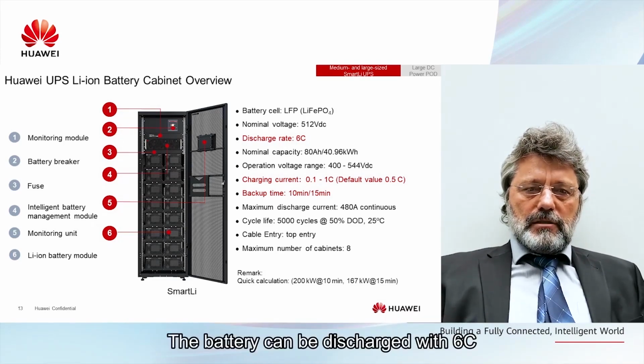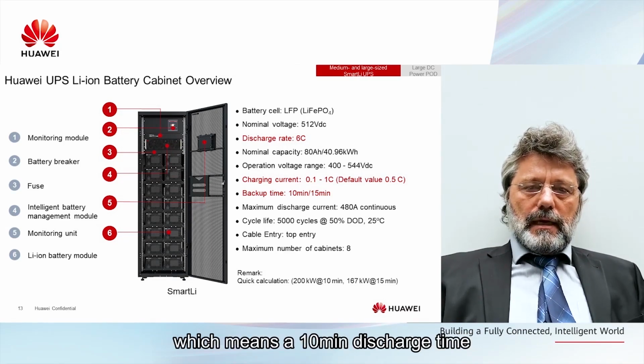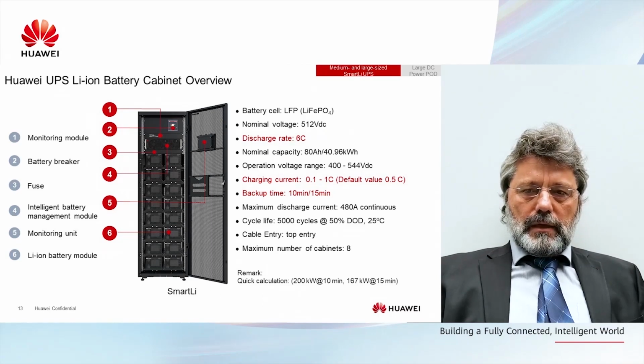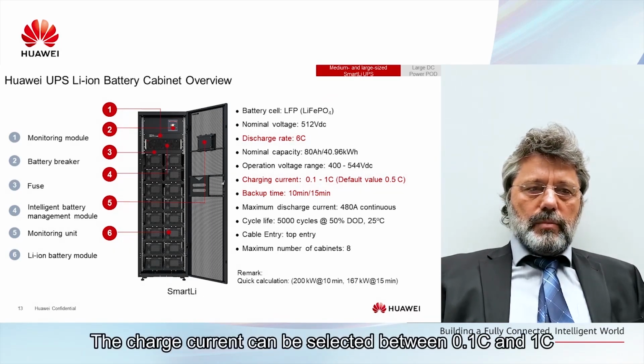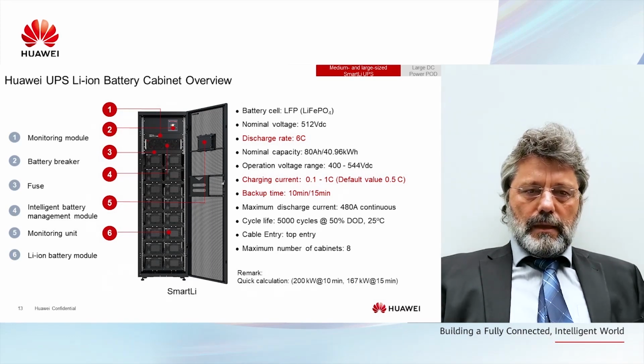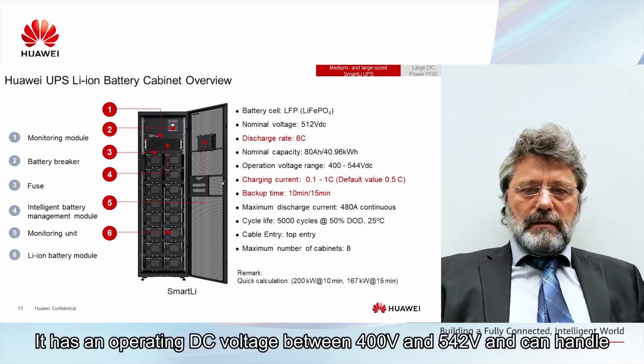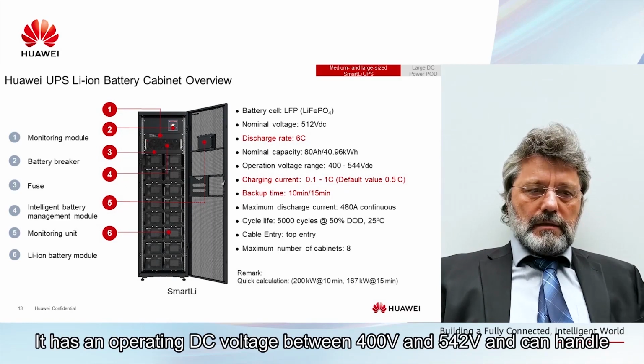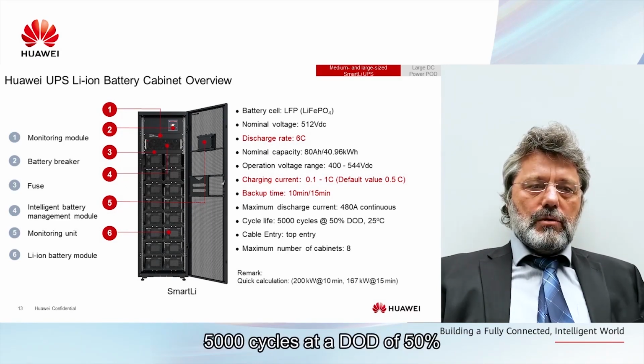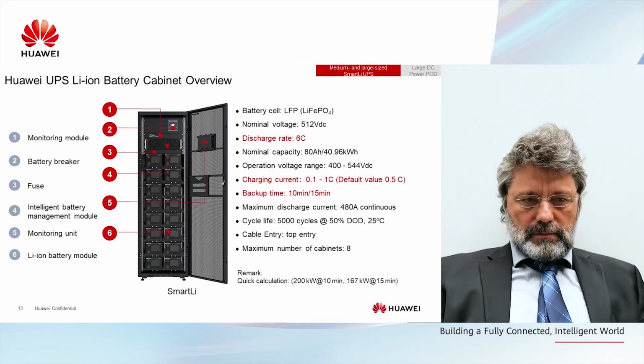The battery can be discharged with 6C, which means a 10 minutes discharge time. The charge current can be selected between 0.1C and 1C. It has an operating DC voltage between 400 volts and 544 volts and can handle 5,000 cycles at a DOD of 50%.